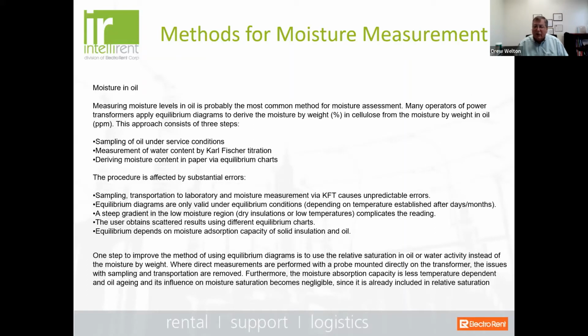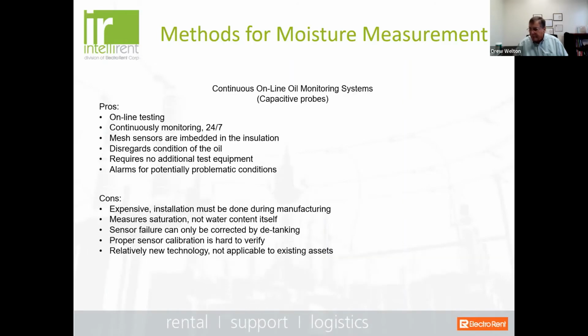We had a situation where we took 5 different oil samples at the exact same time from the same transformer and sent them off to 5 different laboratories. The moisture analysis, the ppm analysis, came back with ranges that were not very consistent. So one thing that you could certainly do is just be very careful in drawing your samples and making sure there's no contamination on the way to the lab as it's being measured.